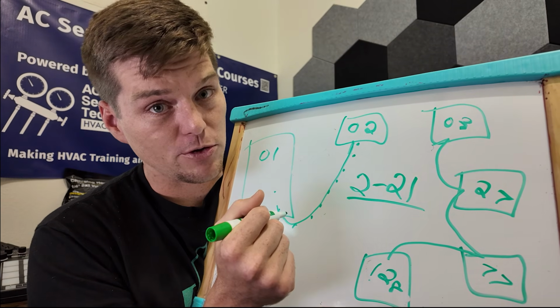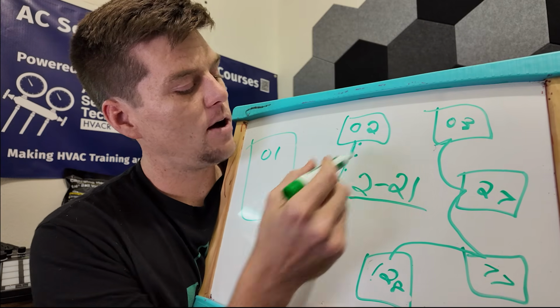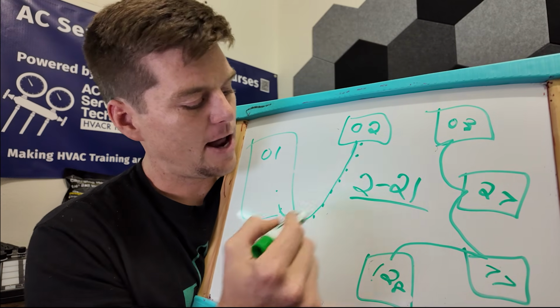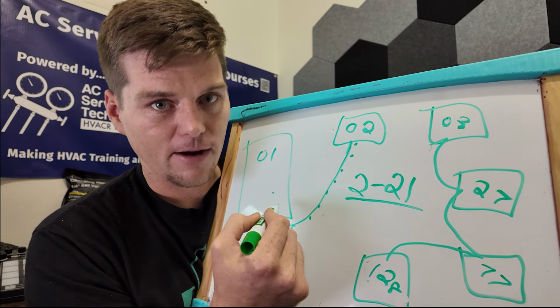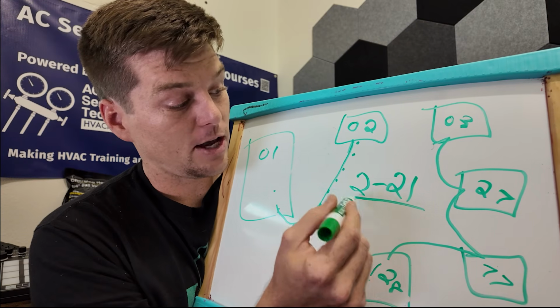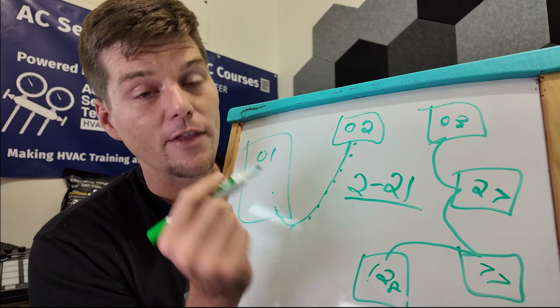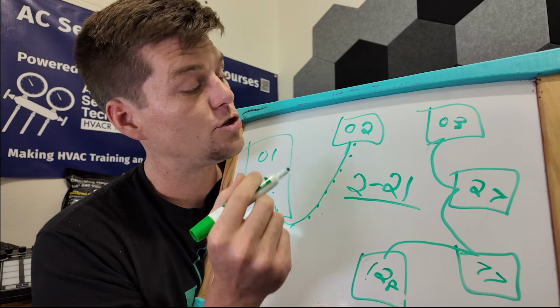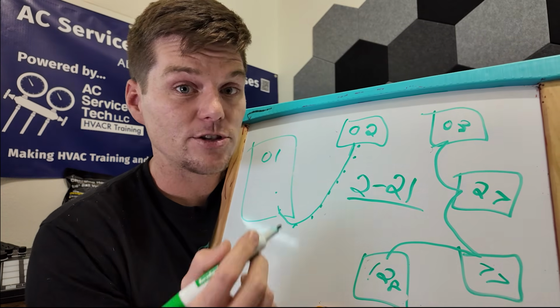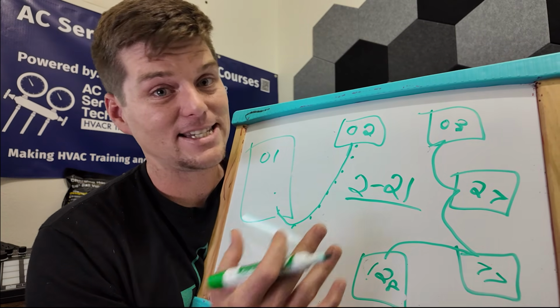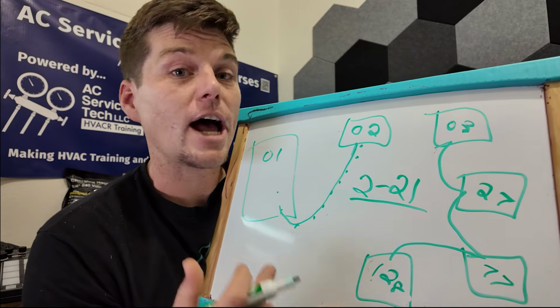So with using setting mode 221, I can then say, well, it's in setting mode 221. I know the wire is connected from front to back here. I've put it into force communication mode right here, refrigerant recovery mode, and now I'm waiting to see what happens. Well, if nothing happens within the first 4 to 5 minutes, it's usually because the indoor unit has noticed that nobody's on the network and it can't see anybody or any signals, so it stops looking.